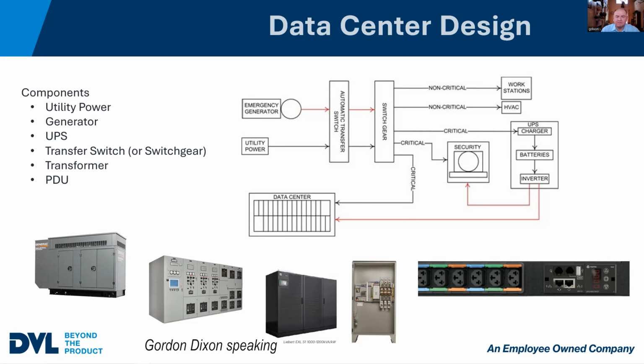There are some other components involved here. You're going to have electrical panels, and possibly transformers if you've got to step down the power. But I wanted to include this drawing just because this is a critical piece. And if you're thinking in terms of, do I need a UPS, do I need a generator, do I need both, and how are we going to integrate those into the systems, this would be one of the starting places. You want to have a general idea about where the load is going to go and what is feeding upstream and downstream of the UPS.